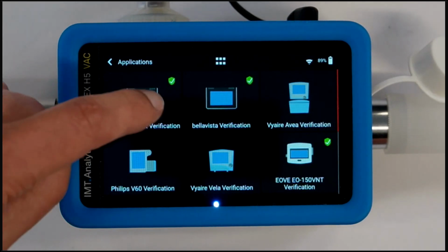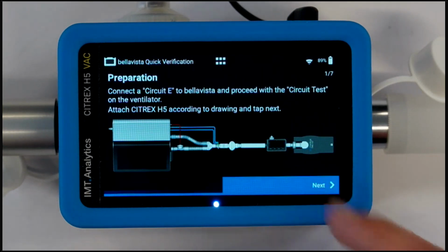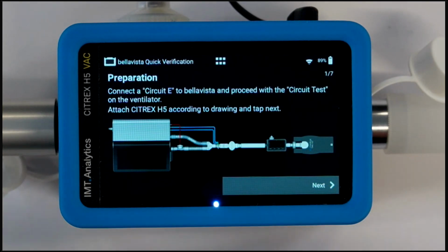The moment when I start a testing app, in the background, it already loads all the correct settings for the corresponding ventilator, because it knows what ventilator we are now testing. So here with the Bella Vista, it loaded the correct gas standard, the correct gas type, the suitable trigger settings, and everything for you. So you can't do anything wrong here. And then it starts guiding you through the testing procedure.